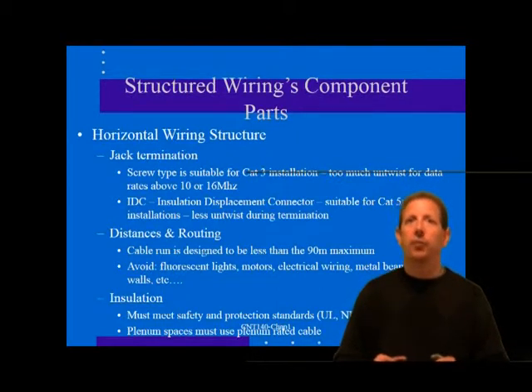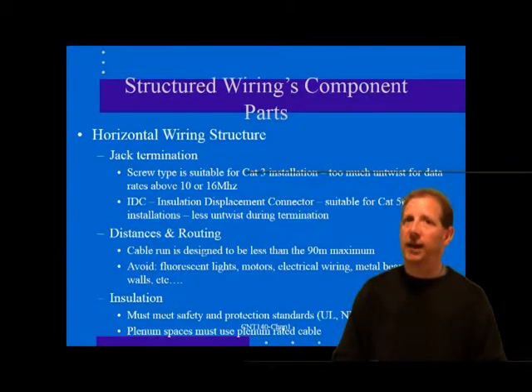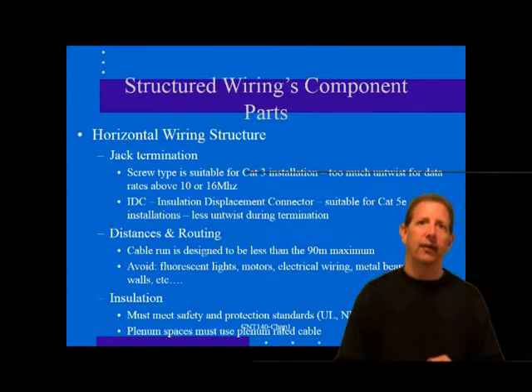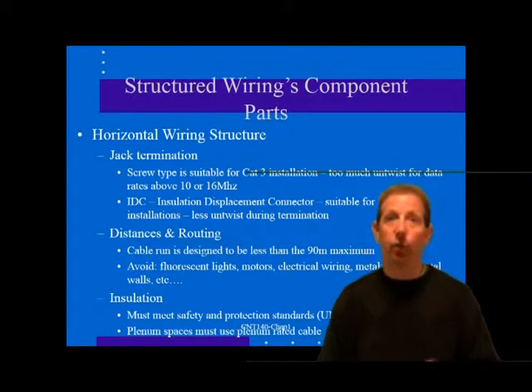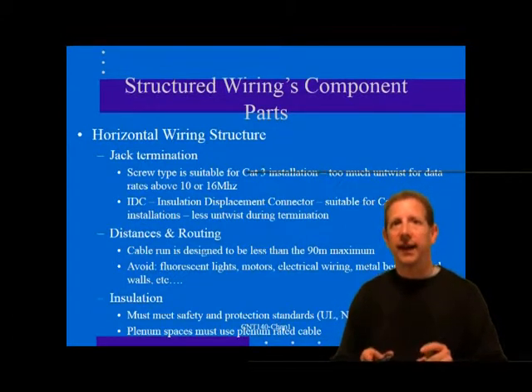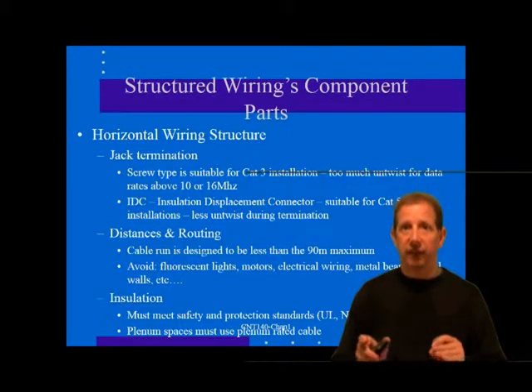Caution should be used when sharing the power wiring channel with data cable. Not only is there a potential safety concern from having a LAN wire so close to power wire voltages, but there may be performance problems, particularly for Cat 5e performance. Some guidelines specify a two-inch or more separation from power wires, while others specify greater distance. Local and national installation codes generally prohibit LAN wiring from being installed in the same conduit as power wires.